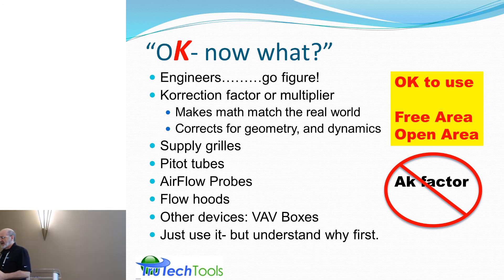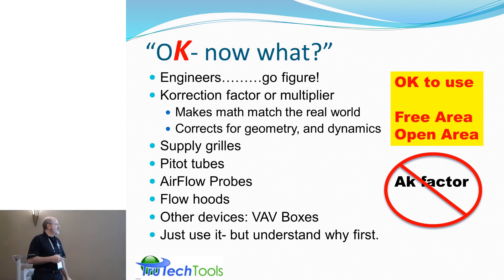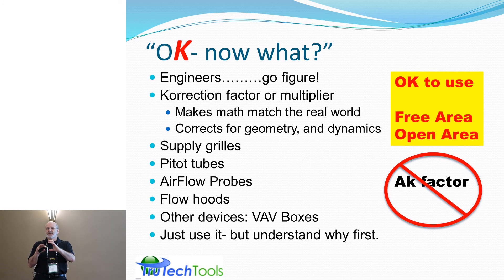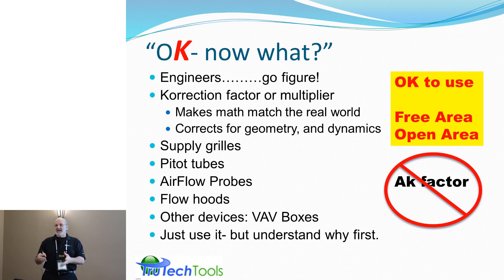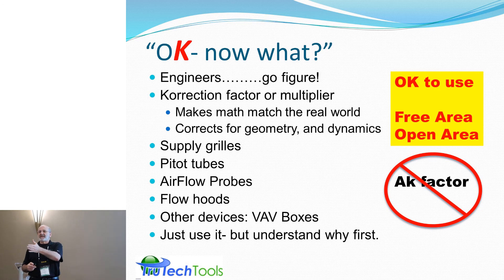Airflow probes have K-factors. Flow hoods actually have K-factors too — sometimes the manometer coupling to the flow hood has a K-factor adjustment because you can use different geometries of flow hoods with different skirt sizes to adapt to supplies and returns. VAV boxes may also have K-factors. All these K-factors are not equivalent — that's the key point. You should use them, but understand why you're using them first.